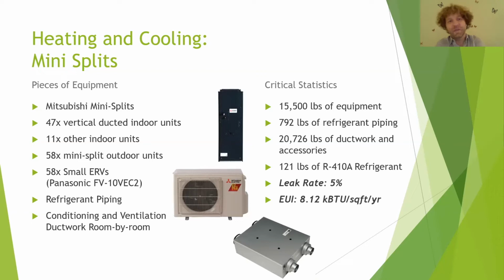The second system is mini splits. We went through and figured out exactly what the system would look like, how much refrigerant piping was in it, how much refrigerant is in it, and the leak rate on a mini split system is a little less because each unit has only one line set. So if anything leaks, it's only in one system. You have a little less leak rate and less than half the refrigerant in the piping.